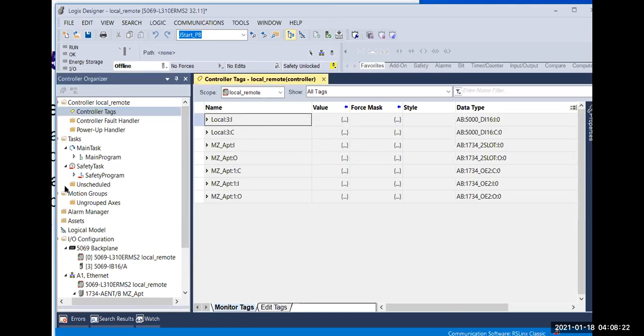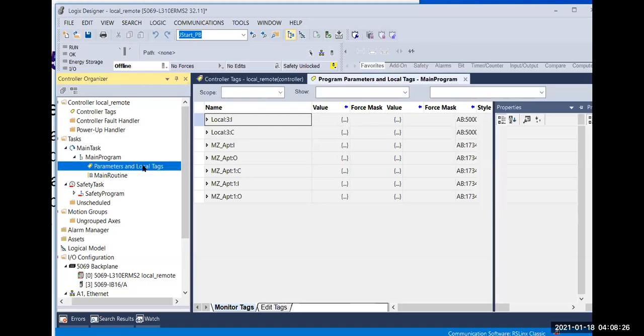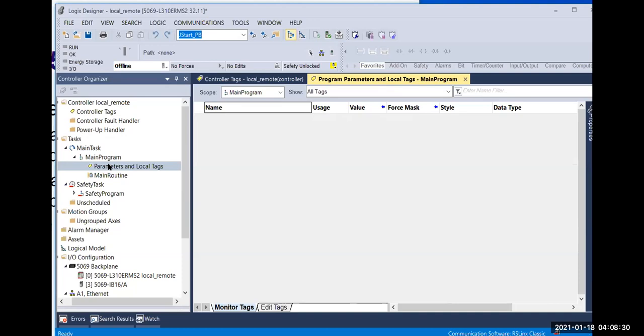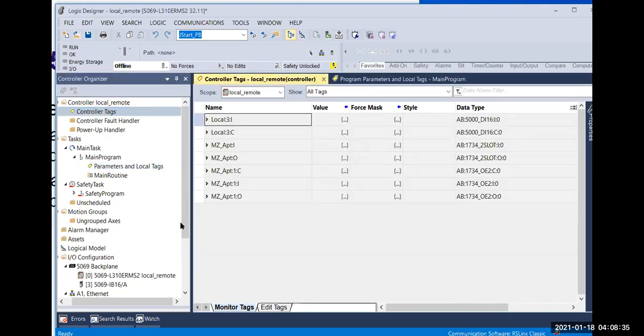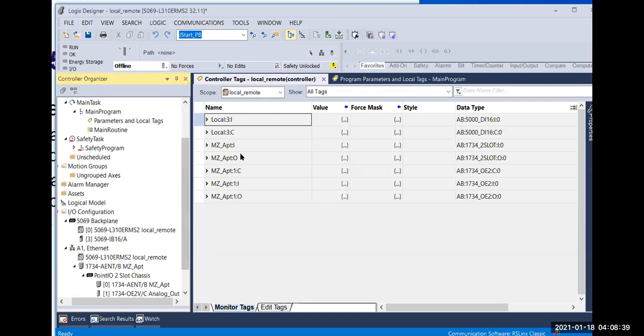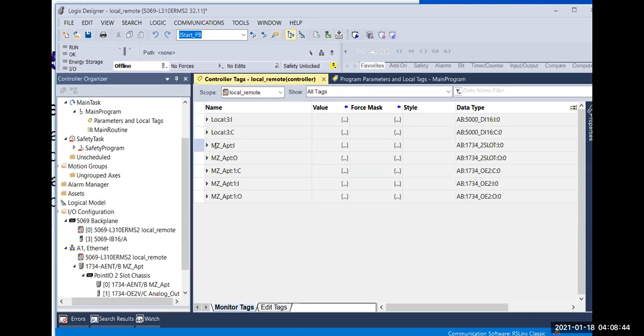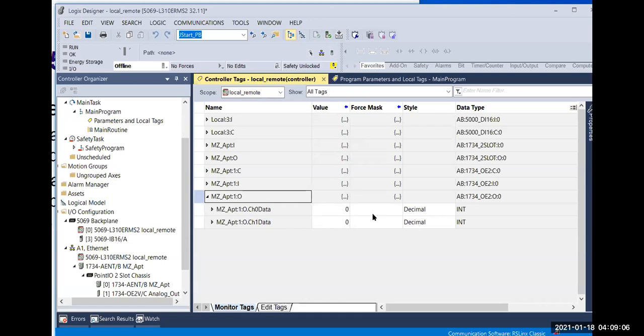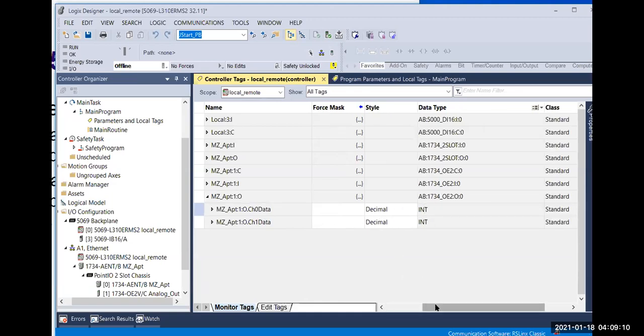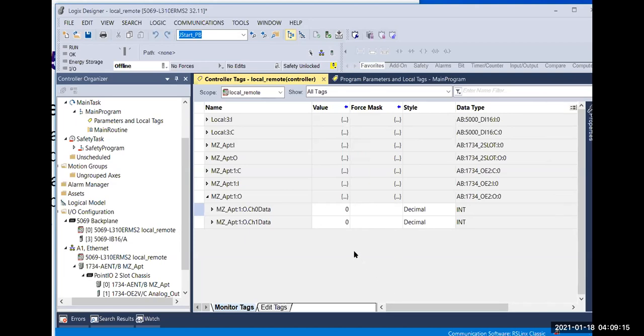I want you to notice this is a controller tag, not a program tag. The program tag is local and not shared by all programs — that's why I/O tags need to be at the controller level. Because of the location (local vs. remote) and the specific features of the module, you can have input or output. For this analog output, if you open the data folder you can see channel zero and channel one data. Also notice that the data type is integer — that means it's analog, not binary or Boolean (zero or one), which would be digital. So the tag really matches up with the module's specific features and location.